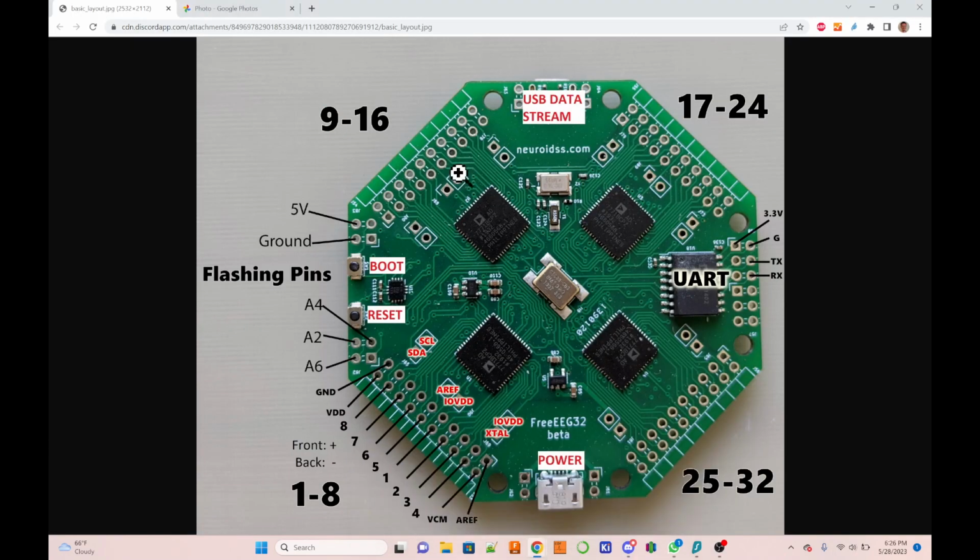Can you swap out your own electrode? Yeah, so I've made a system where it's modular. The amplifier will have spring-loaded pins on it. On the pinout that we have here on the screen, the whole thing will be encased in a housing, so unless you open it up, you're not going to see the board. And there will be spring-loaded pins on here.